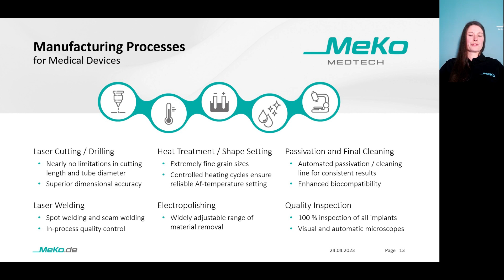A lot of medical devices need to be electropolished, and the machines which we use allow us a widely adjustable range of material removal. For the subsequent passivation, we use an automated cleaning line to reach consistent results and to enhance the biocompatibility of the components. Finally, each part needs to pass quality control. For this, we perform a 100% visual inspection of all implants and own several different automatic microscopes for further controls.